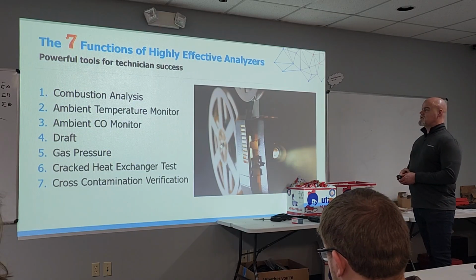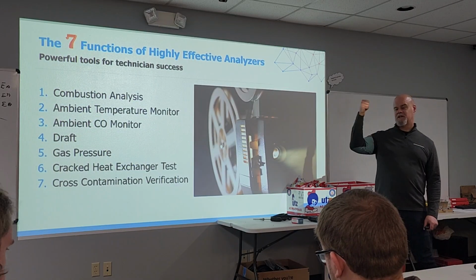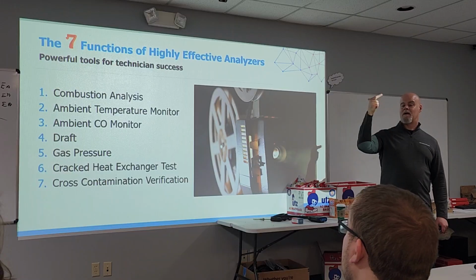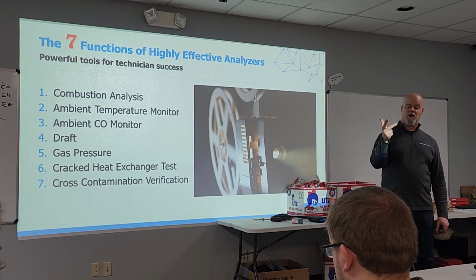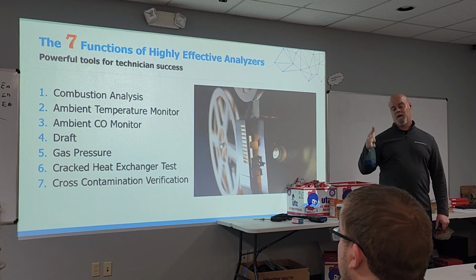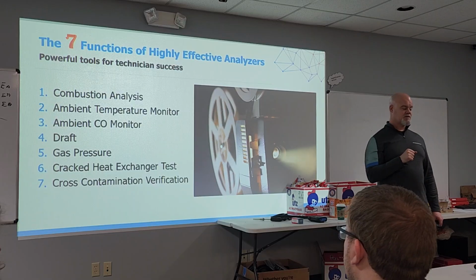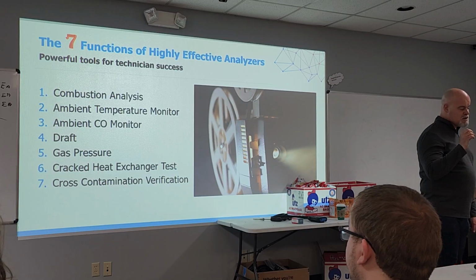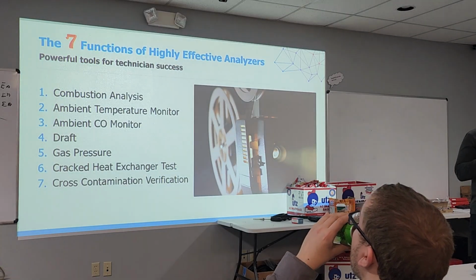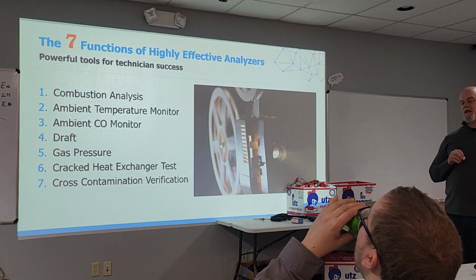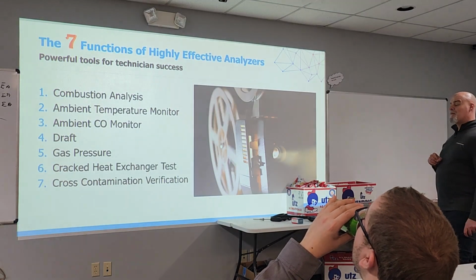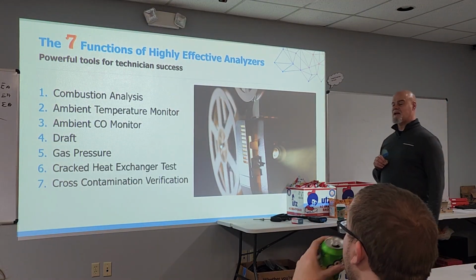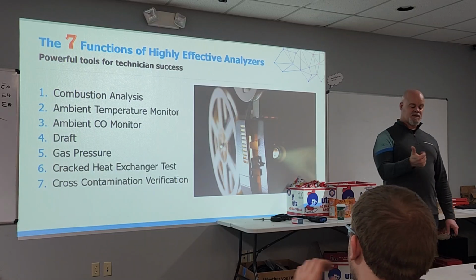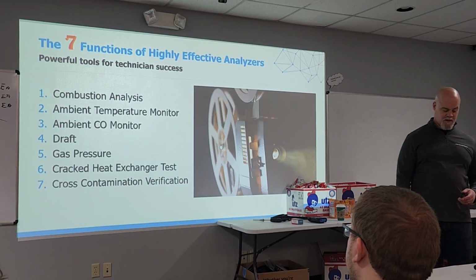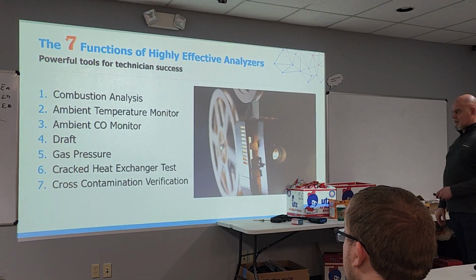Analyzers are 7 tools in one. They do combustion analysis, yes, but they also do ambient temperature, ambient CO, draft and gas pressure, because there's a differential pressure manometer built into each one of these. You can verify a cracked heat exchanger, which I'll cover, and you can verify cross-contamination on a condensing system, which I'll also cover. I'm also going to cover the extensive tentacles this has into the commissioning, diagnostic, and maintenance aspects of your life, as well as some other shenanigans.